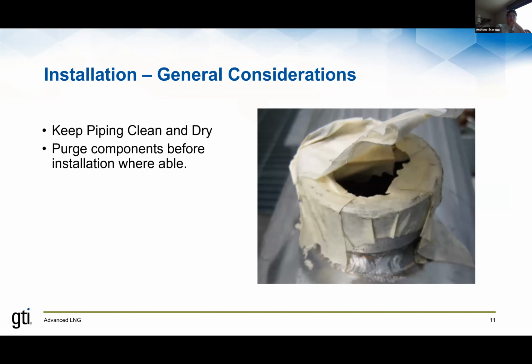Installation, general considerations. When you're installing components in an LNG plant, remembering that LNG is minus 260 degrees, any moisture in that LNG will freeze on contact with it. So you really want to keep things clean and dry. You want to purge components before you actually introduce LNG into them, purging them to reduce the moisture in those components, to dry them out, so that you don't have any residual moisture that would freeze out and possibly harm equipment.